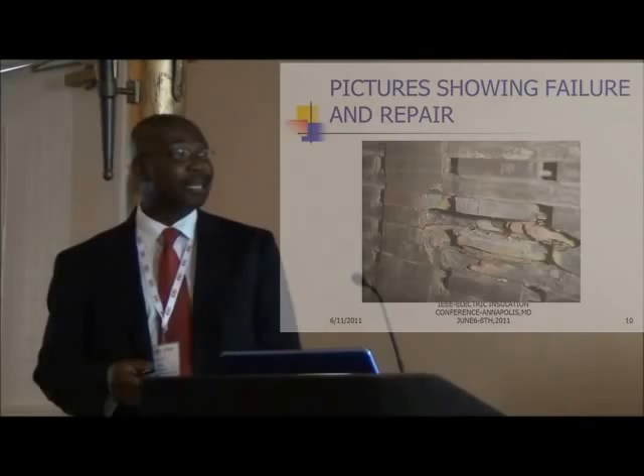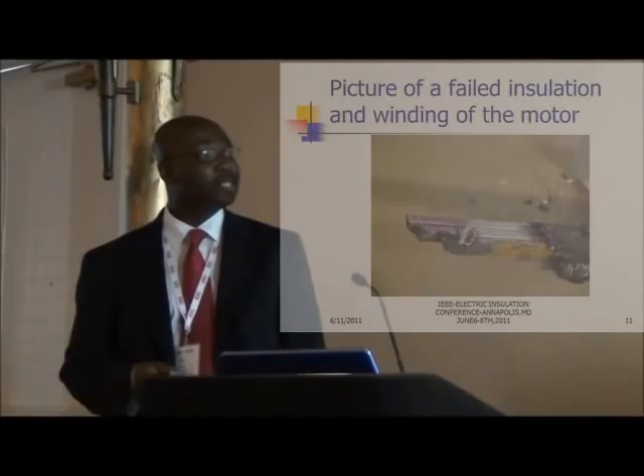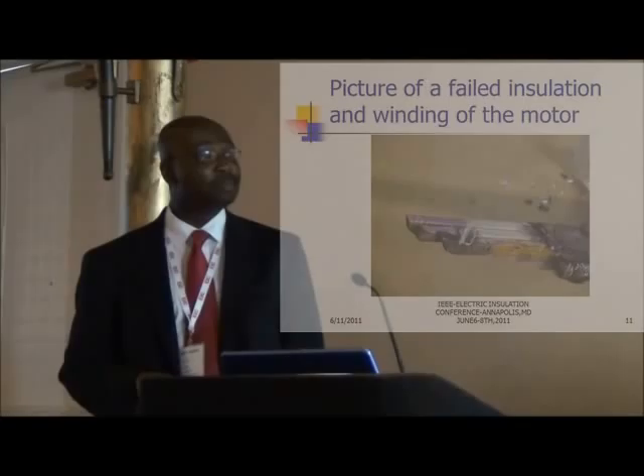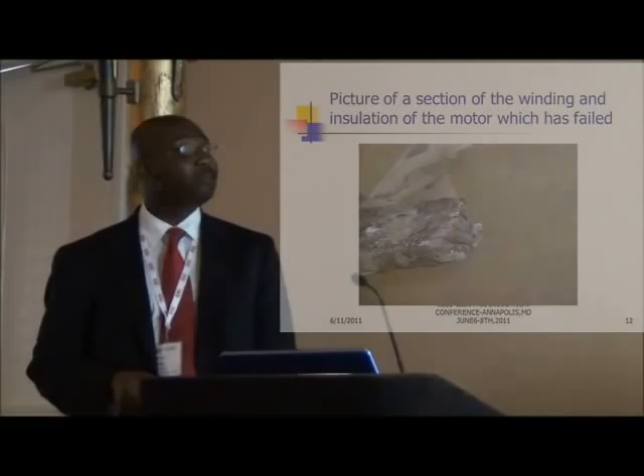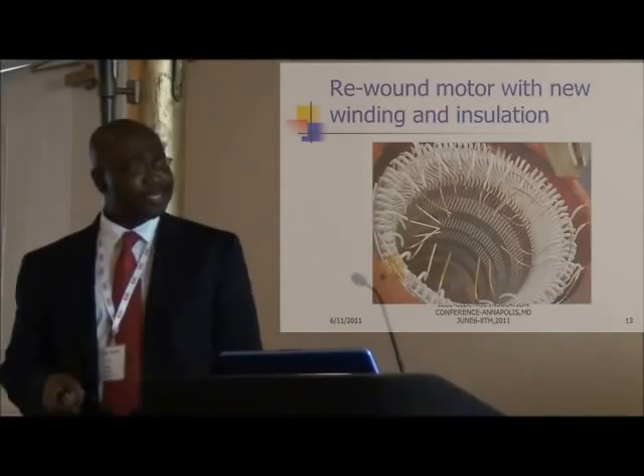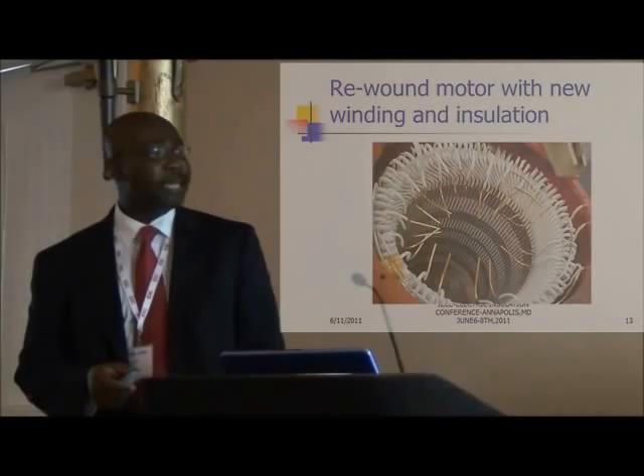Looking at the damage pictures: you can see a section where both the winding and the stator core were completely gone. The next image shows a section of the delaminated and failed winding, showing the individual coils that make up the overall part. Another image shows a section of the winding and stator of the failed motor. The final picture shows after the old winding was completely stripped out and a new winding was installed.